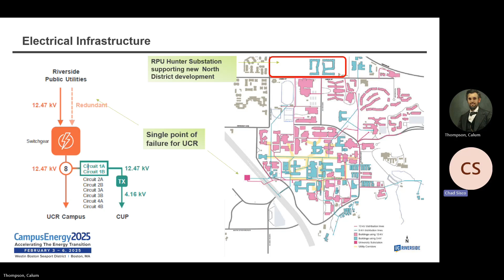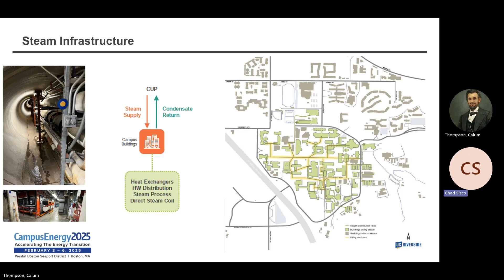For our steam infrastructure, the main point I want to bolster on this slide is that we have utility corridors located throughout the entire campus. As you can see in the picture, there's a highlighted portion of the utility corridors, and this was basically the staple of our analysis, in that we can reuse these tunnels to run our new hot water piping and remove the existing steam piping, which will help costs and alleviate disruptions to campus.